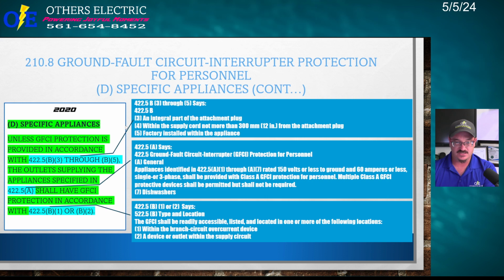Okay, so let's go through this little by little. 210.8D, specific appliances, GFCIs. Okay, so unless GFCI protection is provided in accordance with 422.5B3 through B5, the outlet supplying the appliance specified in 422.5A, shall have GFCI protection in accordance with 422.5B1 or B2. So let's go through this one by one. Unless GFCI protection is provided in accordance with 422.5B3 through B5. So this is what that says.